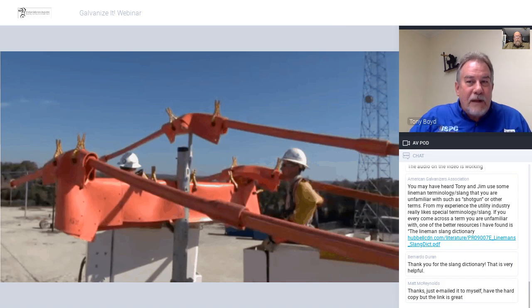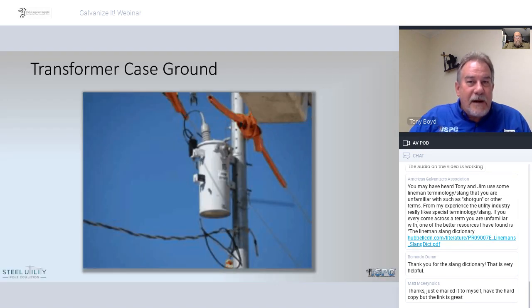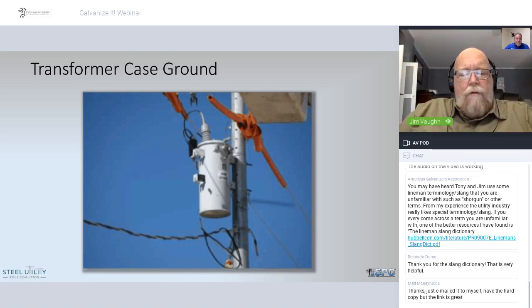Tony, back up to that one slide. I want to point out one thing for both the utility linemen and for the manufacturers here. If you see right here, this is a tank ground on the transformer. There's also a tank ground right here. And then right here are the 3 secondary bushings for this transformer.